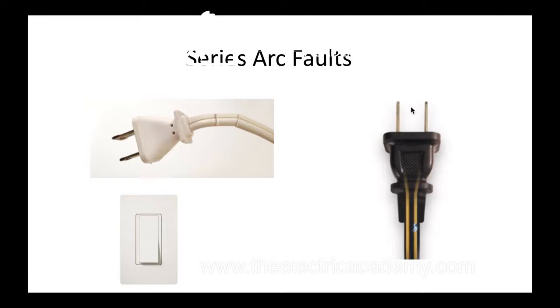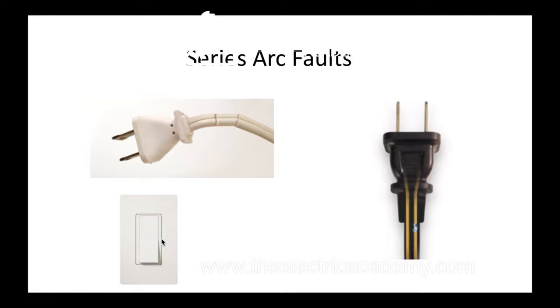Some areas where we see series arc faults are cords that get frayed, cut up, or beat up and old. Another very common area that you see series arcs are switches. When we have arc fault protection, we need to make sure that it can recognize the difference between a fault and a switch, because when you switch — especially when you're dealing with inductive loads — there's always a bit of an arc. A switch will always have an arc; you've probably seen that little spark.